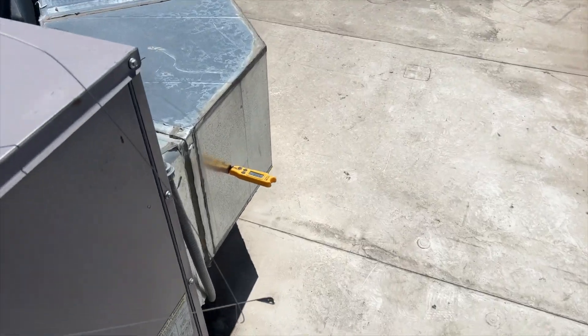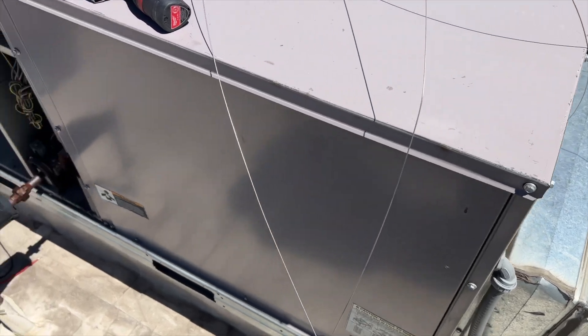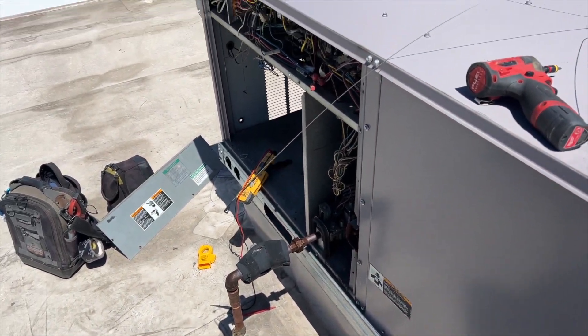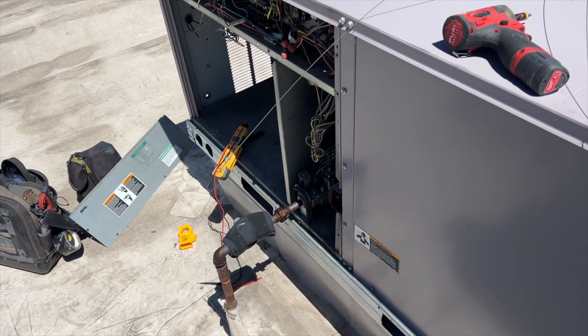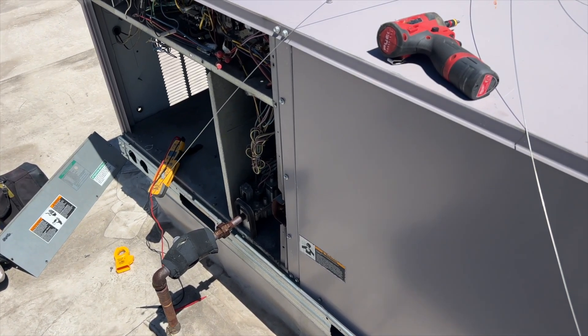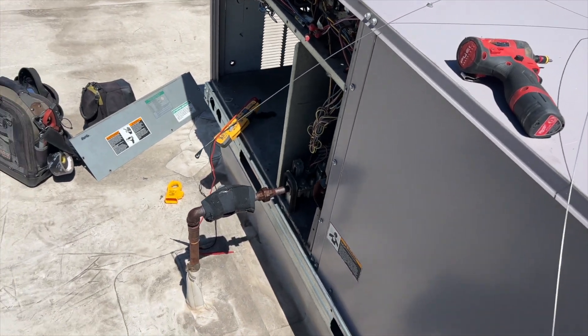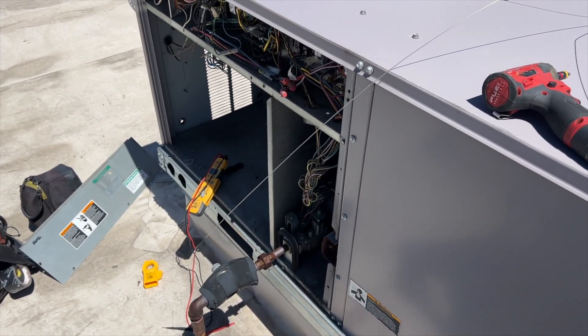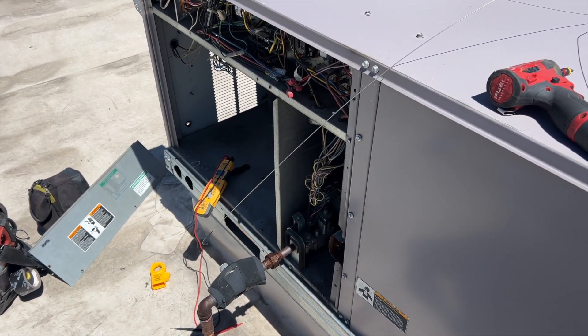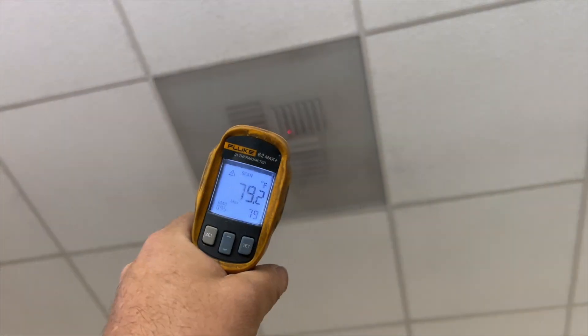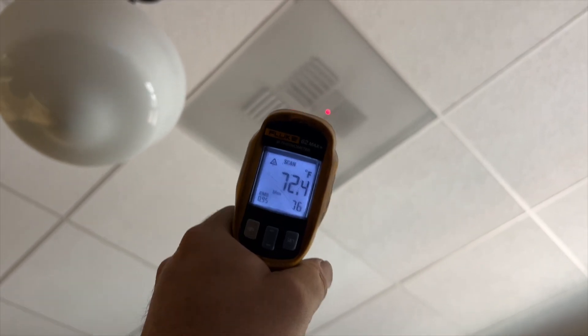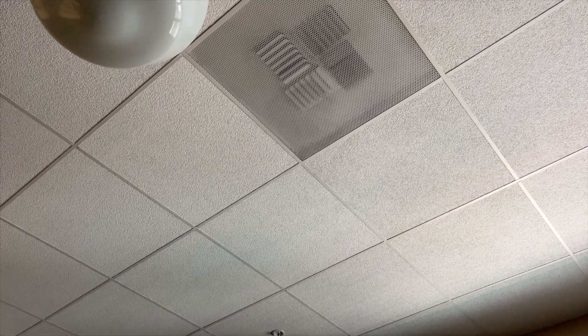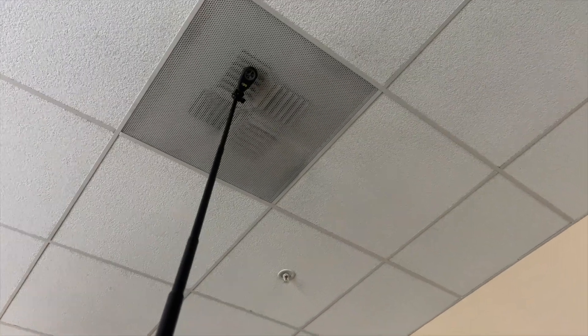I'm bummed out because it's cooling normally. I still have no airflow, so we probably got a dead zone damper or something. That's gonna be fun because I have no idea where the zone board or any of that is, so we got to go into the ceiling now. So now I gotta walk like 20 miles away to go get my ladder. We know it's running, we know we have airflow and I got nothing. I got a little bit here but that could be a little bit of leakage. We got zero airflow as you can see.